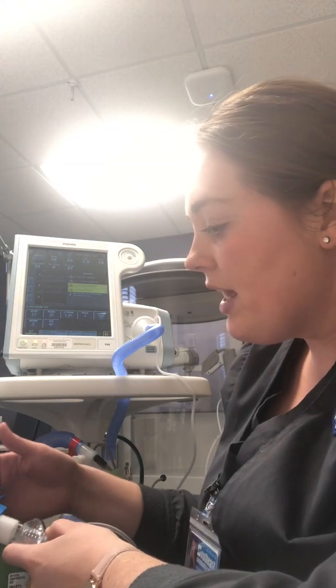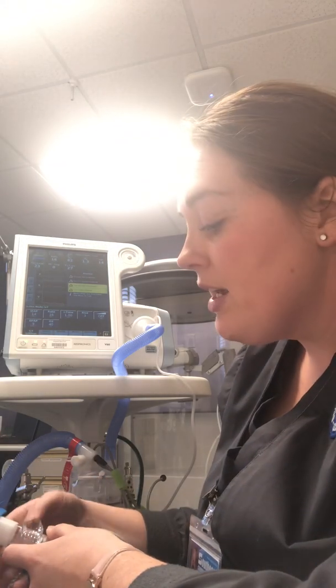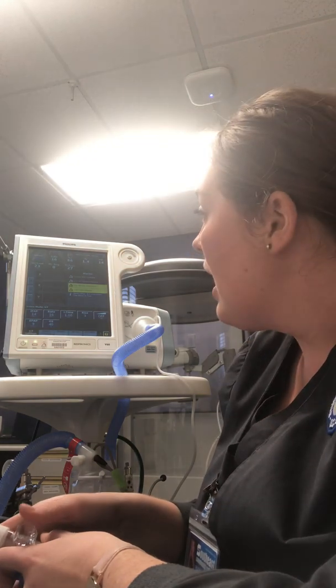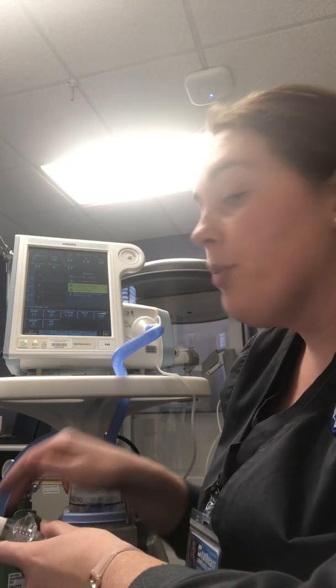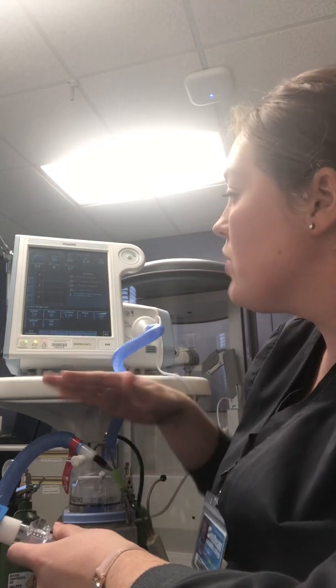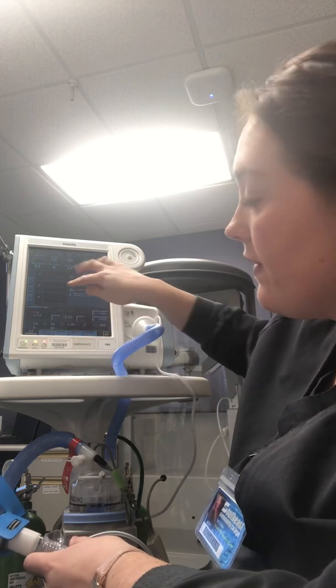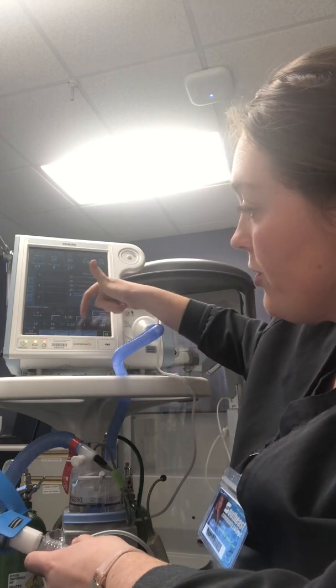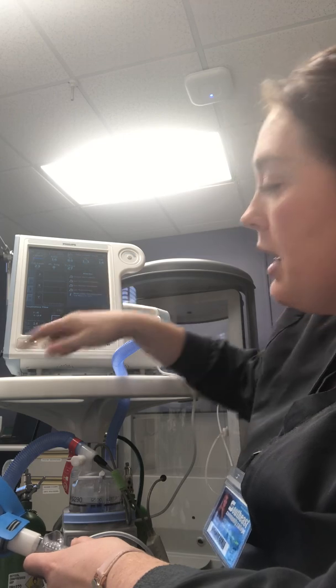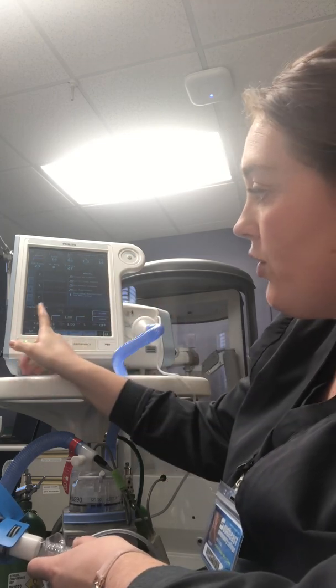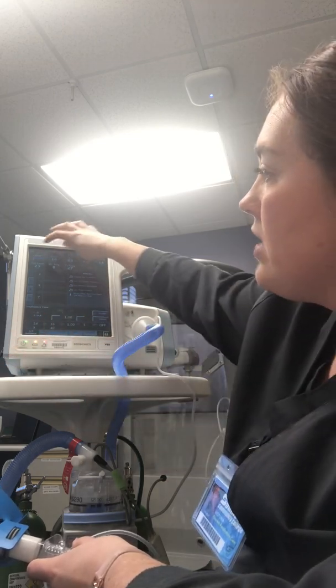And you can also set a ramp for your patient, which is going to allow your patient to get to IPAP a little bit slower or more quickly depending on how you set your ramp. So to change any of the settings, all you do is click on them. You'll see there's an arrow on either side. You just adjust accordingly.